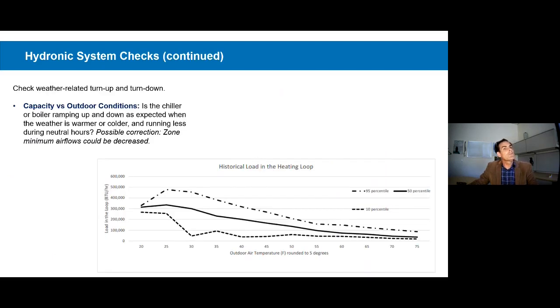We can also look at historical system capacity. This graphic here shows the historical capacity of a heating system, a boiler system, again, versus those outside air temperature conditions in 5-degree bins. So notice again that odd phenomenon that the highest heating load occurs not in the 20-degree bin, but in the 25-degree bin. Again, defying the laws of physics there.